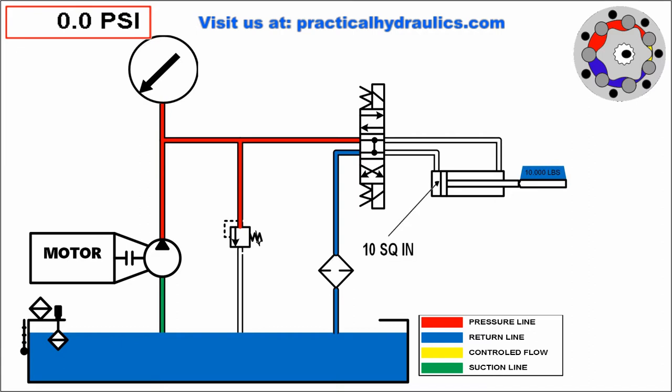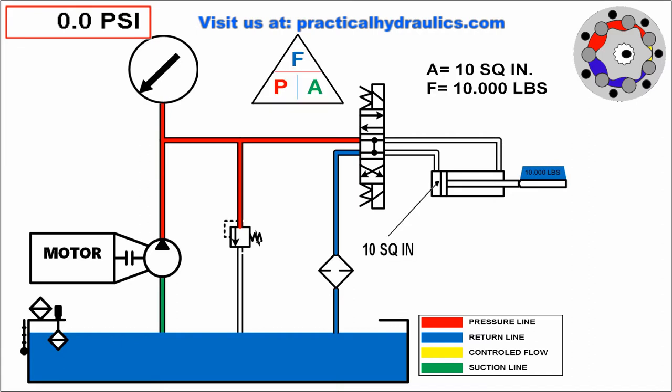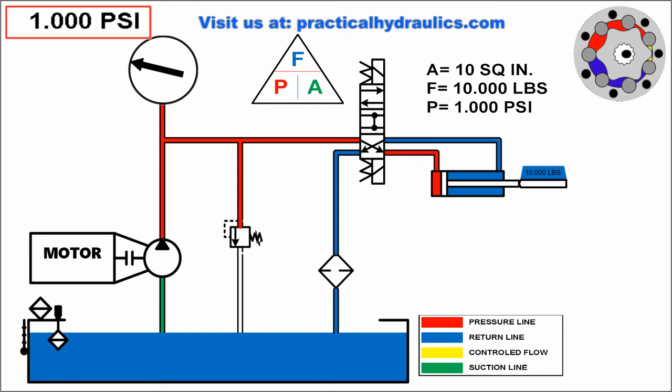In our illustration, a 10,000-pound force gives us a load-induced pressure of 1,000 psi. Based on our formula, when the cylinder is extended, the required pressure to move the 10,000-pound load is 1,000 psi, less frictional forces.